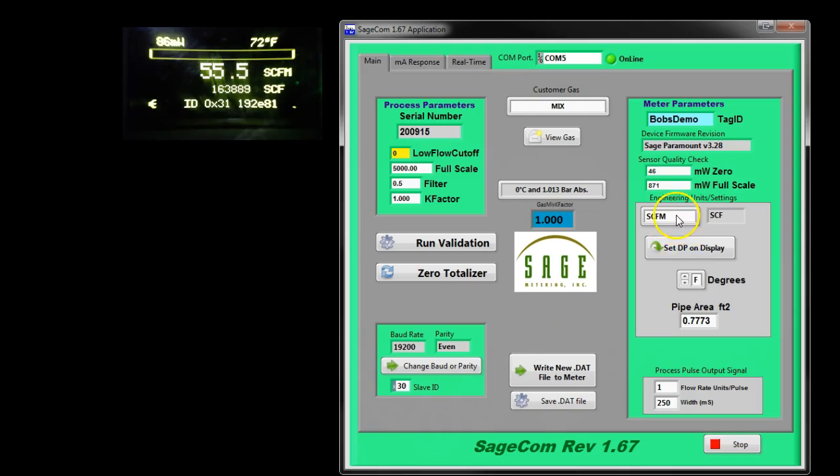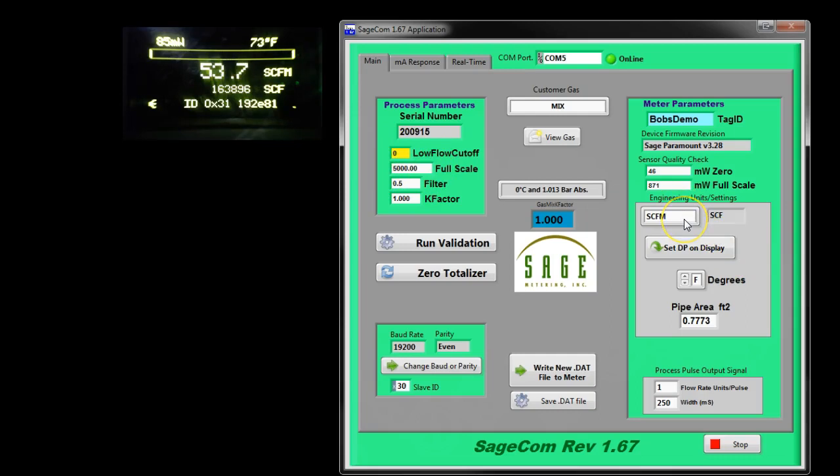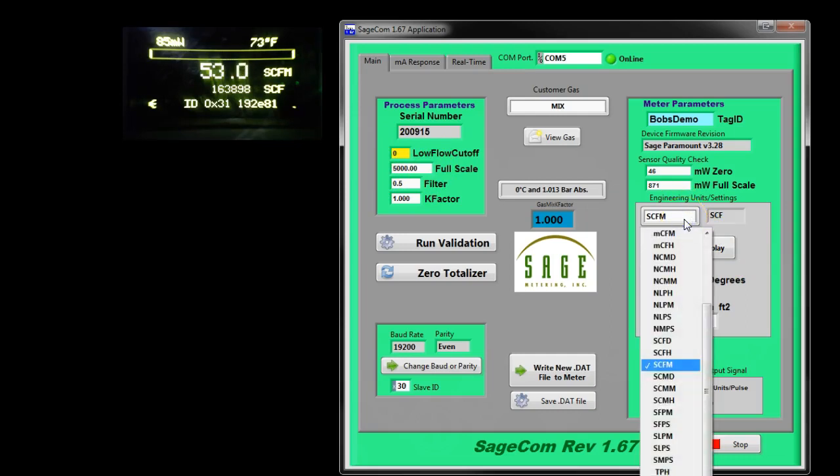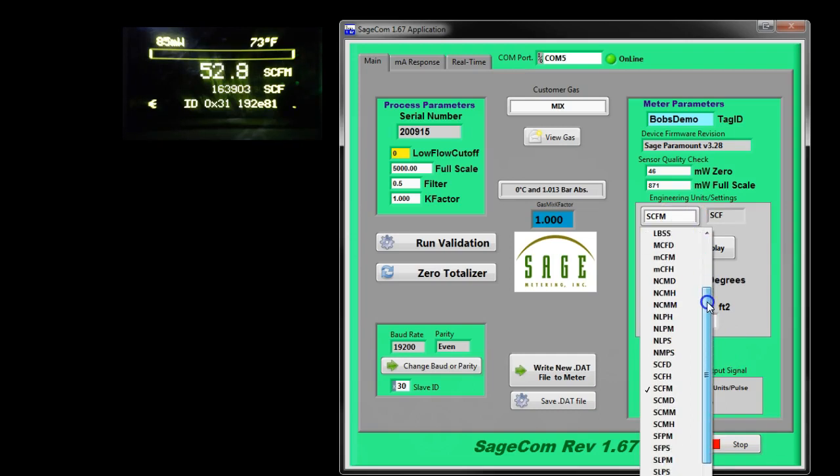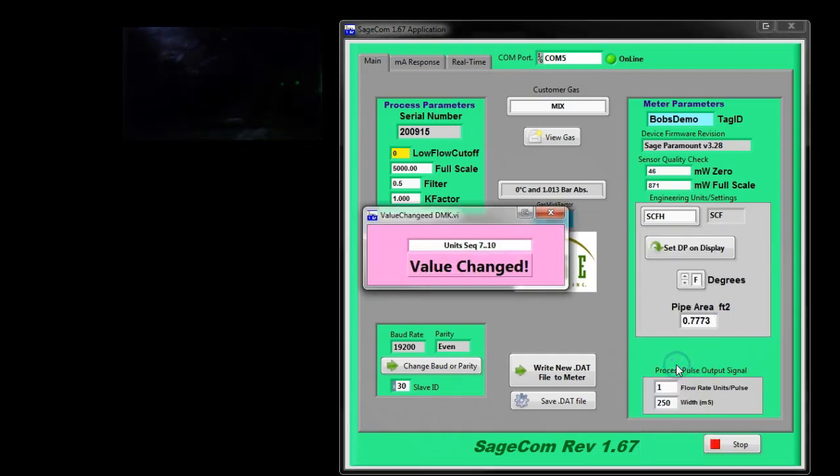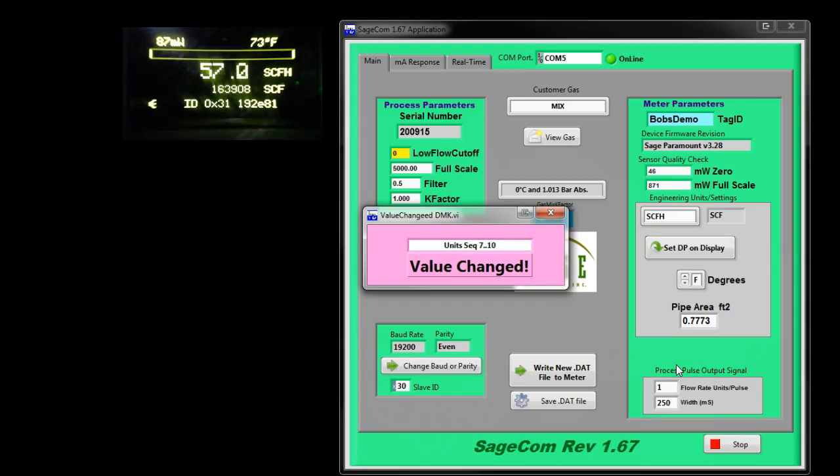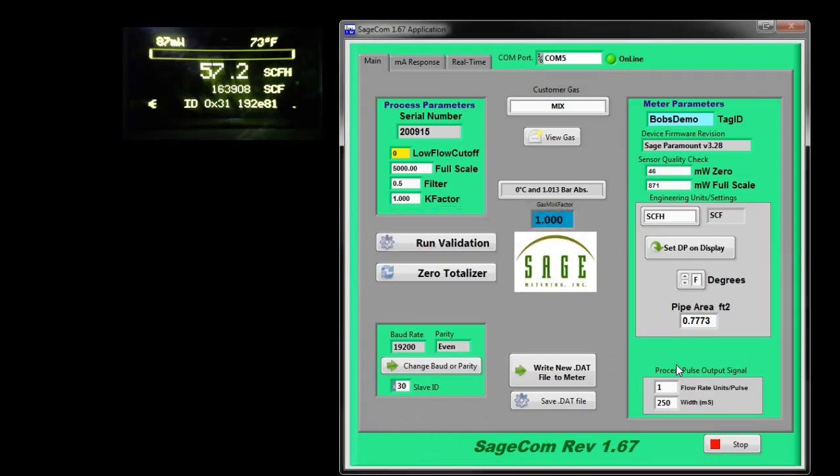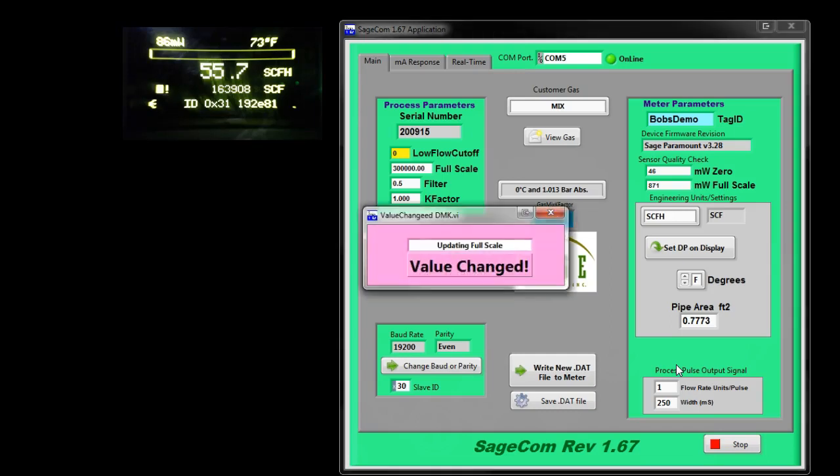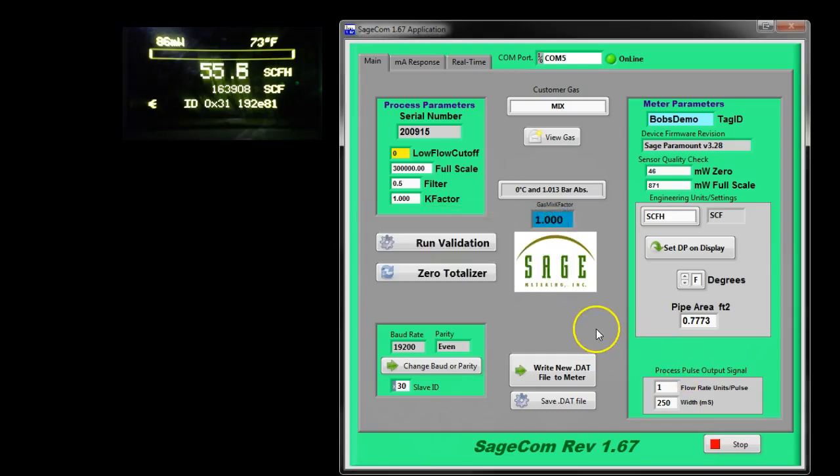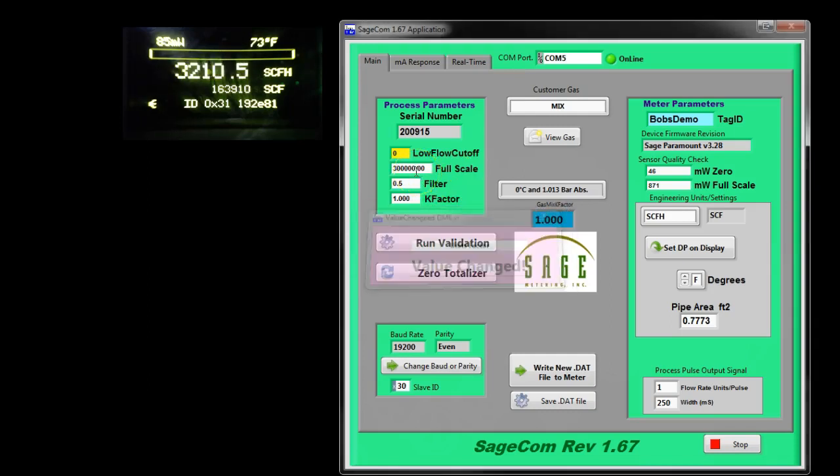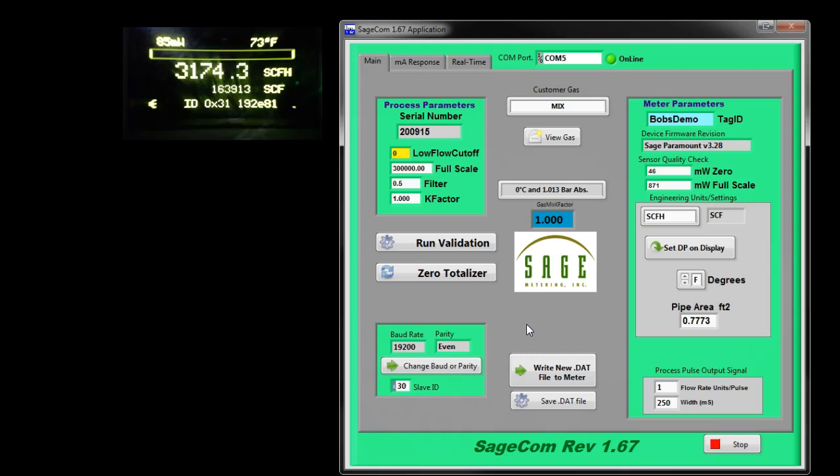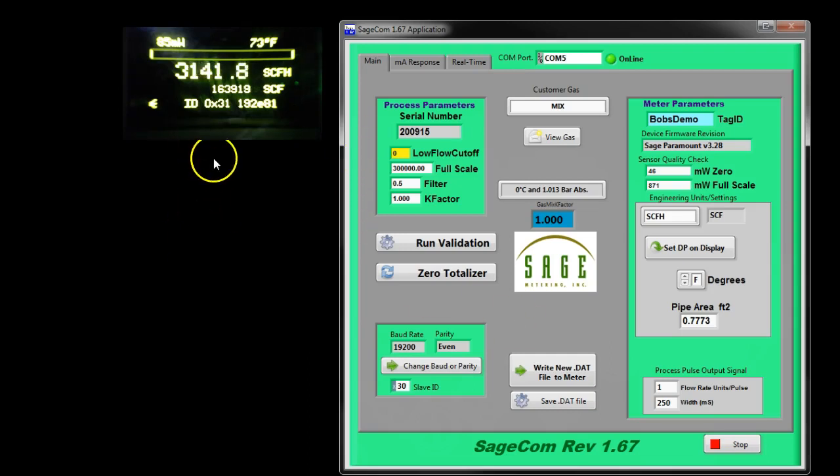So let's get started. Suppose you want to change engineering units. Notice this meter has a full scale of 5000. Notice it's reading 50. So let's change it to SCFH. Well, firstly, I want to show you all of the choices. There's kilograms, pounds, normal cubic meters per hour and so forth and so on. I'm going to click on SCFH and then I'm just going to wait. And notice the pop-up menu that shows you it's converting to a new full-scale value change and here we are at 300,000 SCFH, which is the same full-scale in different units as 5000 SCFM, and of course the flow rate is responding accordingly.